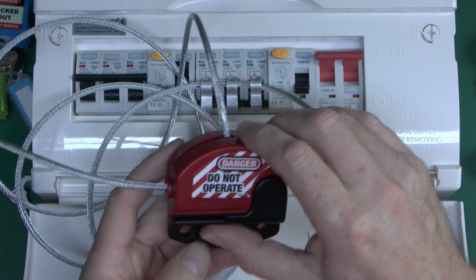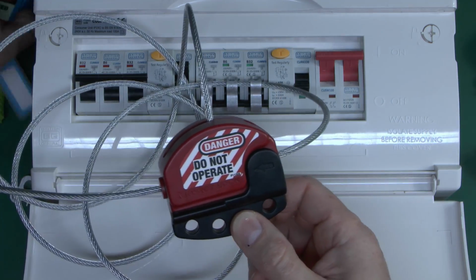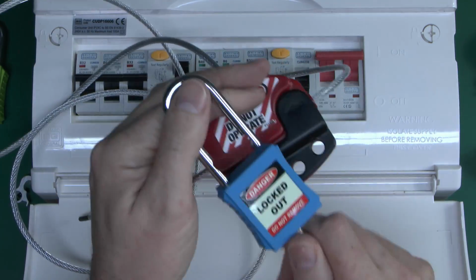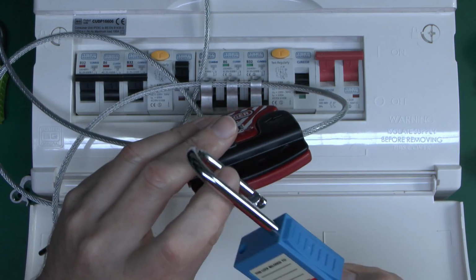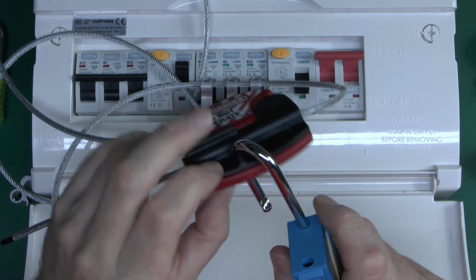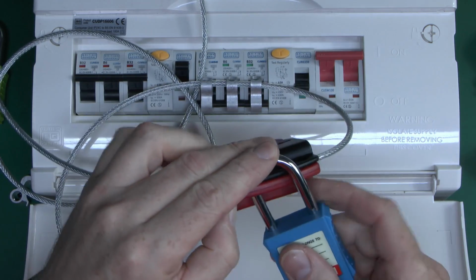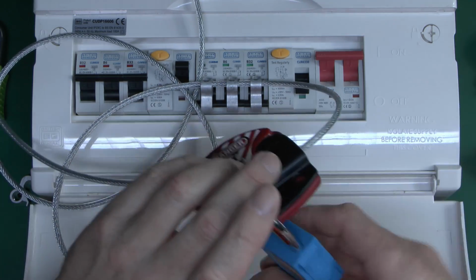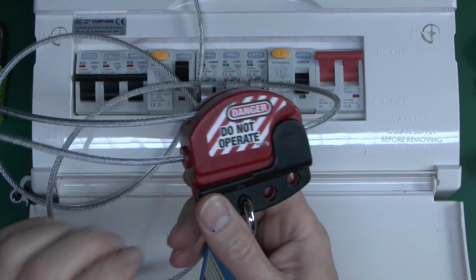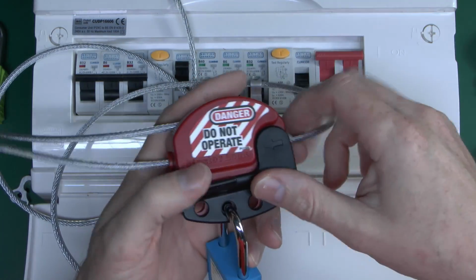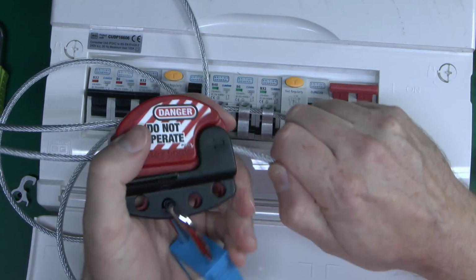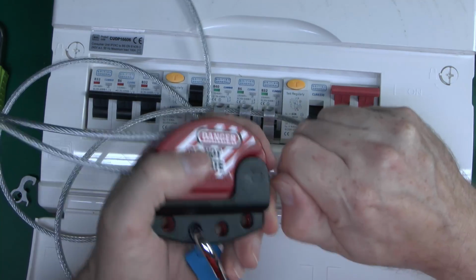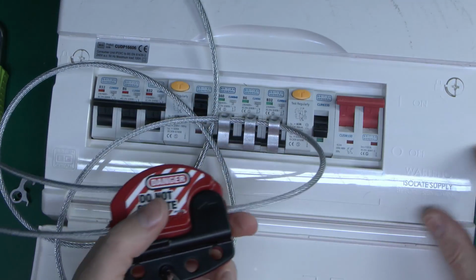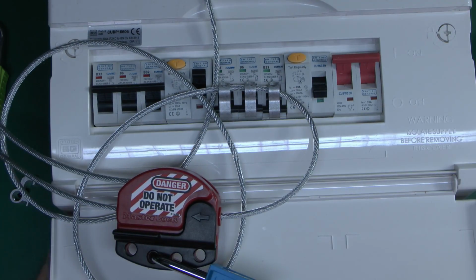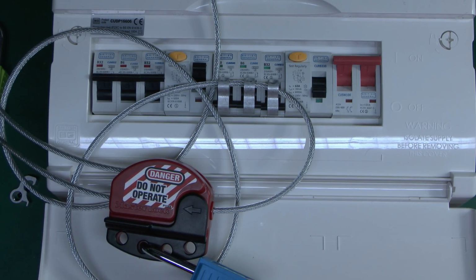Then, when it's closed in that position, the padlock goes through here. Let's use this blue one for that. Again, you can attach your warning notice and things as well. So that goes through there, and the padlock prevents this from being opened. When this cable is in position and that's locked, you can't pull it out. It's securely locked in position. So that's a way of doing multiple ones of those.